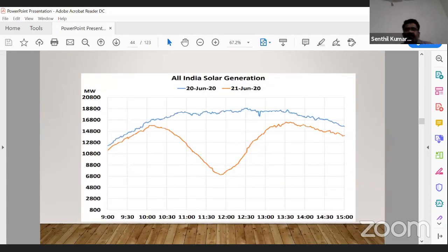The solar variation over that 10-hour period reduced generation from around 15,400 megawatts to 6,900 megawatts, then suddenly during the 12-13 hour period there was a steep increase reaching 16,000 megawatts. So we had to increase hydro generation, then reduce it based on hydro pick-up, backing down based on solar generation increase - balancing demand and generation effectively, managed by the grid operator, the system operator, throughout the day.